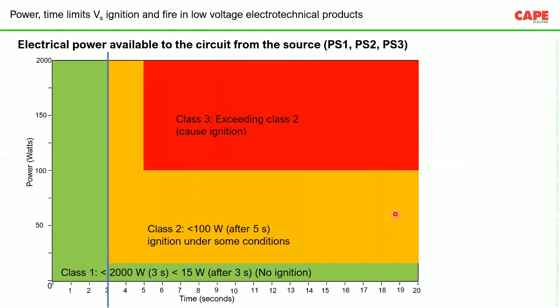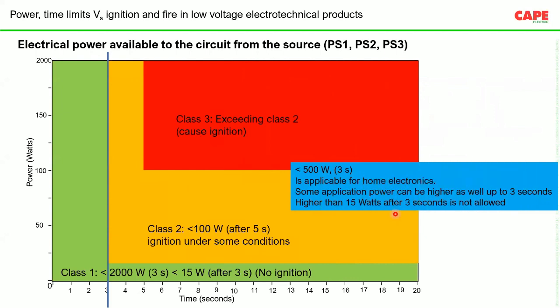Now, with respect to fire, there are a few concepts included in the design standards. One of the concepts is, for example, in the figure which you are seeing, the green color, power in watts. It is nothing but the power dissipated due to a fault. Whatever the maximum size of the power, let us say 4,000 watts or 2,000 watts, if the fault is cleared within 3 seconds, the chance of ignition of fire is quite less. Or if the heat dissipated is less than 15 watts, even for a longer duration, then the chance of ignition of fire from electricity is quite less. But limiting the heat dissipated to less than 15 watts is quite difficult.